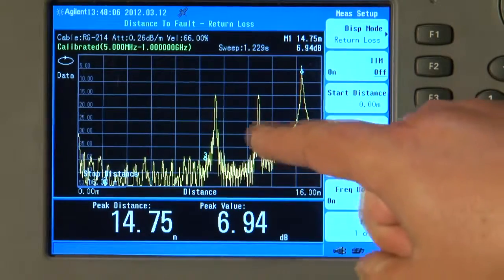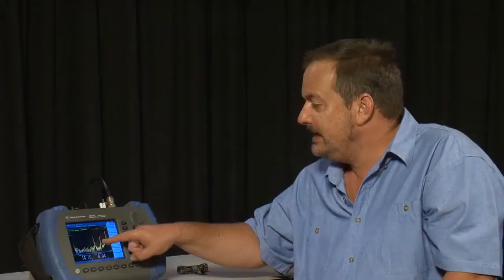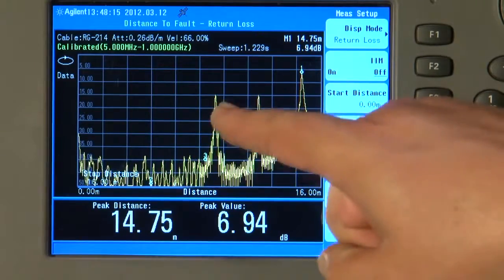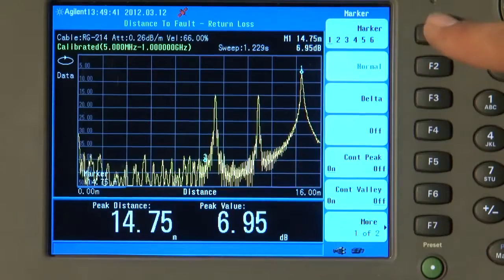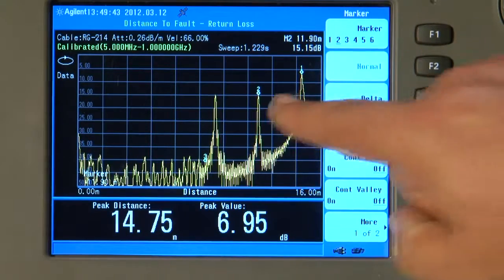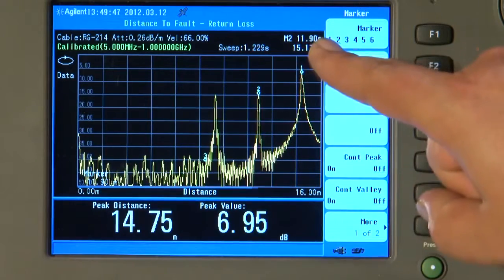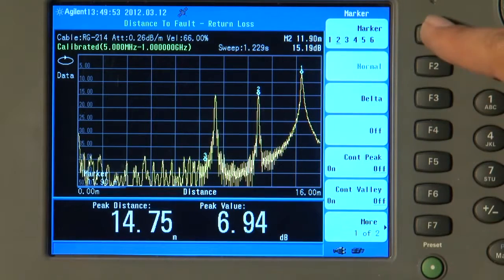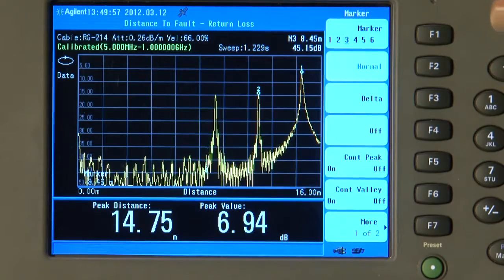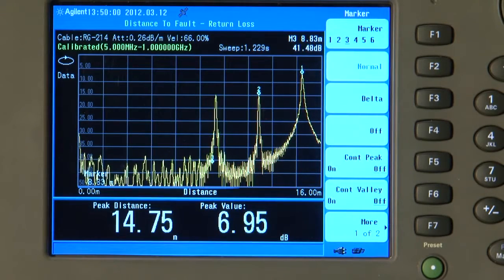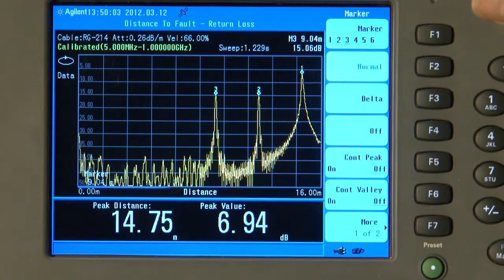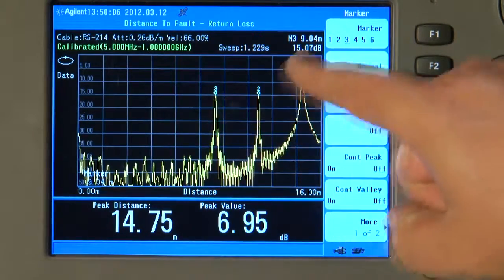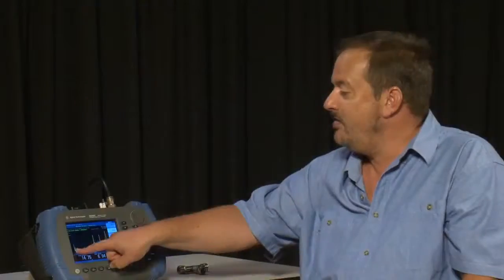But here you can see two very clear faults in the cable. Now, I know those faults are there because I made up this cable from, in fact, three lengths of cable and used some poor quality adapters to simulate some cable faults. So let us press Marker and turn on Marker 2. And you can see that discontinuity there is at 11.9 meters and is a fairly poor return loss of about 15 dB. And I will turn on Marker 3. And let us just line that up with the other discontinuity there. That cable break there, or cable fault, is at 9.04 meters from this point here.